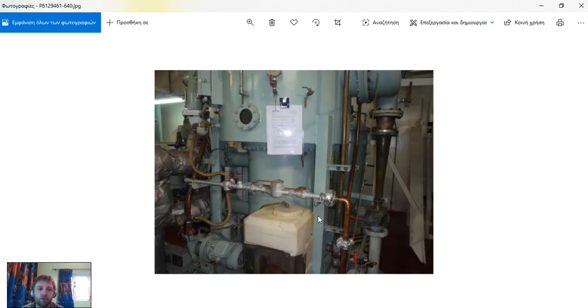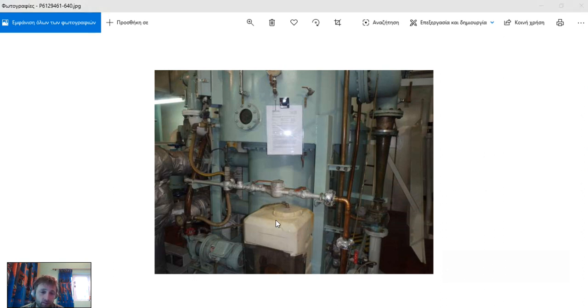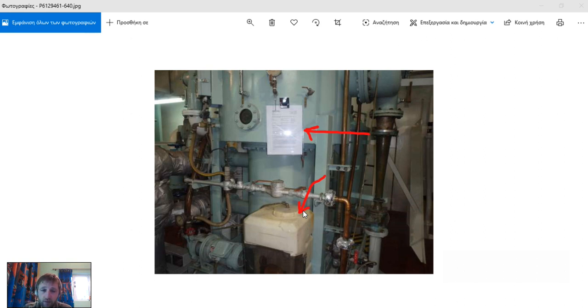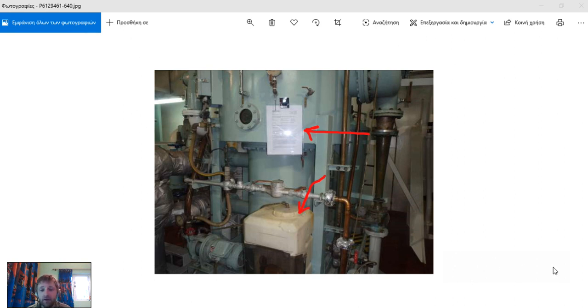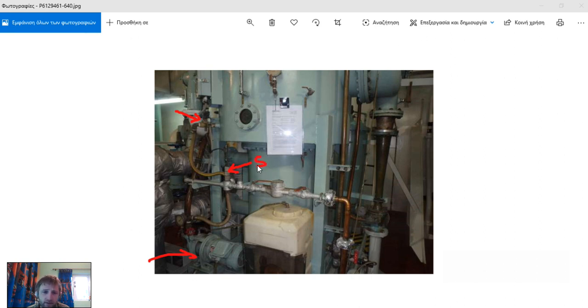Posted here close to our evaporator, this is our fresh water generator. We have the chemicals that we use for the evaporator to protect from the salts. We have our distiller pump here, our salinity sensor here. We also have a solenoid valve here. In case our salinity sensor reads more than the set point of PPMs that we have set from this monitor, it will cut the supply.